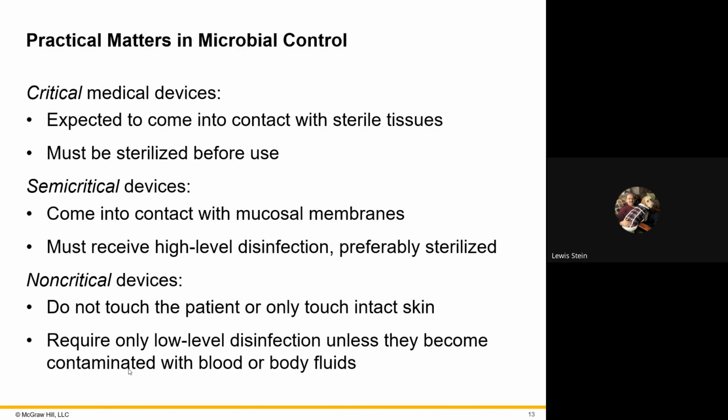What's changed in this slide, and it's still on a lot of the PowerPoints, is that there are levels of disinfectants. So, for instance, when you talk about a critical device, it's one that comes into contact with the inside. Inside is not your mouth, unless it breaks the skin or the lining in your mouth. Inside is not necessarily your throat, your esophagus, going down your alimentary canal, into urinary materials, all of those types of things, because they have a lining.